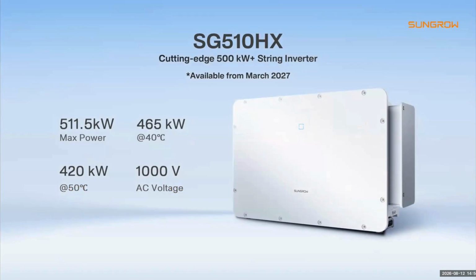So let's start with SG510HX. Its maximum output power reaches 511.5 kilowatts, with 465 kilowatts at 40 degrees Celsius and 420 kilowatts at 50 degrees Celsius. It also introduces a 1000-volt AC architecture. Higher inverter power and higher AC voltage allow fewer inverter units, lower current, reduced cable requirements, and higher power density. So SG510HX is not simply a large inverter. It enables a different system architecture for the next generation of utility PV. This model will be available from March 2027.